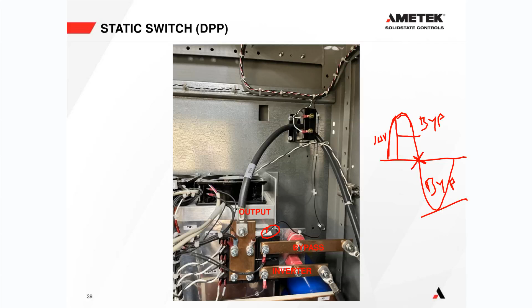If you have a sine wave, SCRs do not switch off by removing a gate signal. SCRs will only switch off at the zero crossing point of a sine wave. So if you are on inverter at this point here, and then at this point here you want to transfer to bypass, what happens is both the inverter static switch and the bypass static switch will be on at the same time until we get to this zero crossing point. After that, we will be on bypass only. So it is always going to be a make before break transfer. It's nearly impossible, unless there's an issue with the SCRs themselves, to have a transfer between inverter and bypass that causes a blip on the load. That's the design of the static switch.